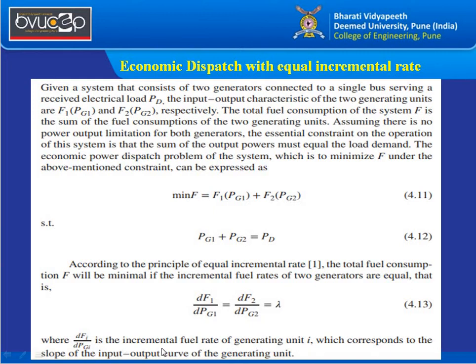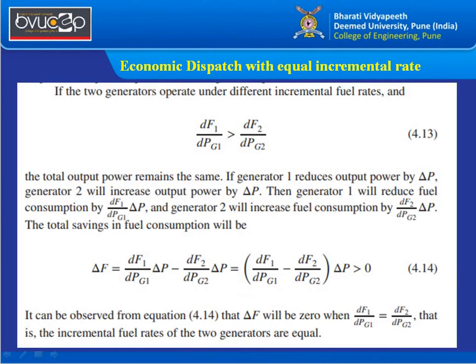The term dfi/dPgi is the incremental fuel rate corresponding to the slope of the input-output characteristics. If incremental costs are unequal, adjusting the dispatch — reducing output of generator 1 by ΔP while increasing generator 2 by ΔP — maintains total power balance. Generator 1 with less power has less fuel consumption; generator 2 with more power has more fuel consumption. The total change in fuel cost, ΔF, will be greater than zero unless incremental rates are equalized.